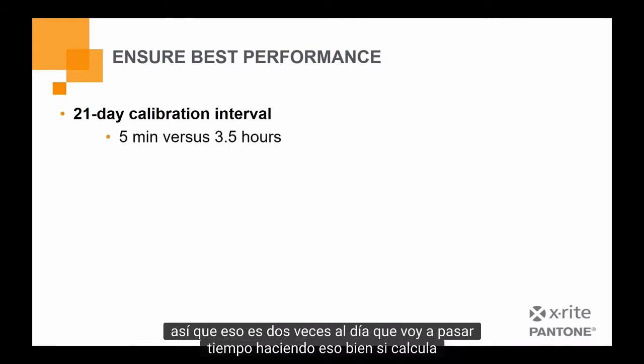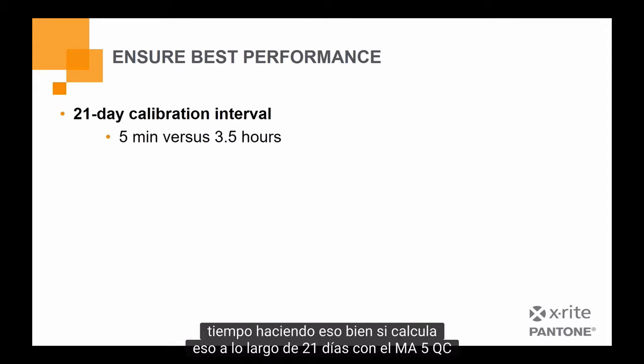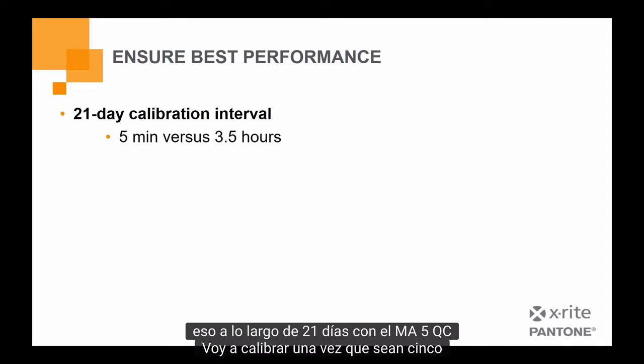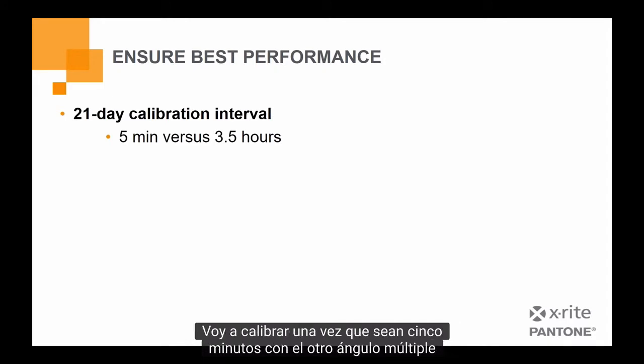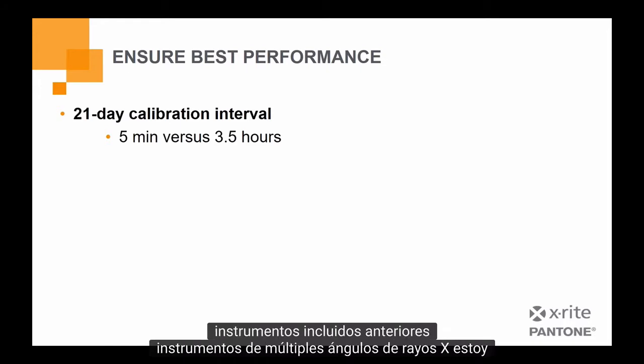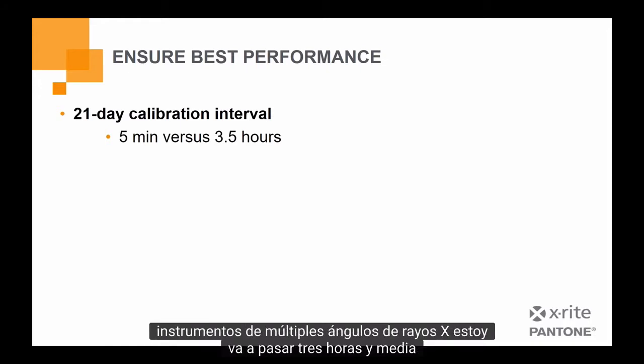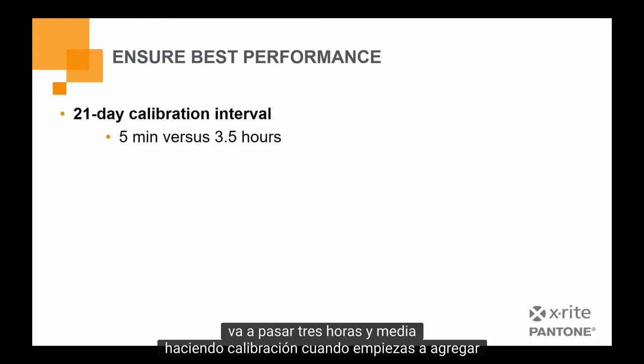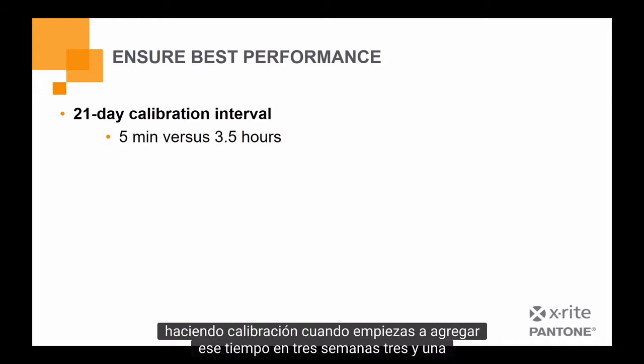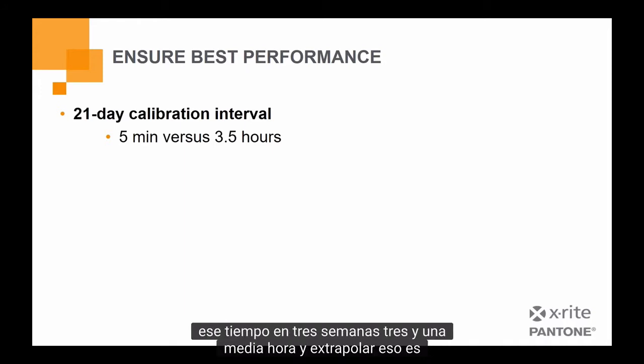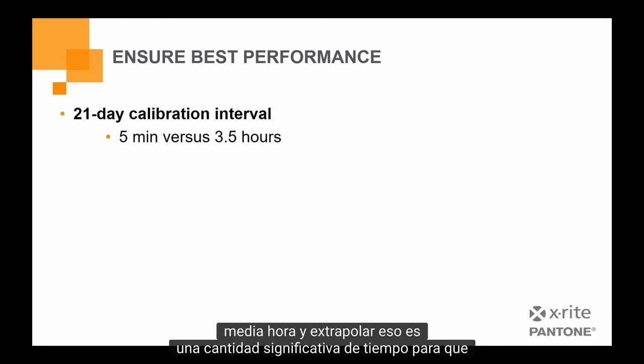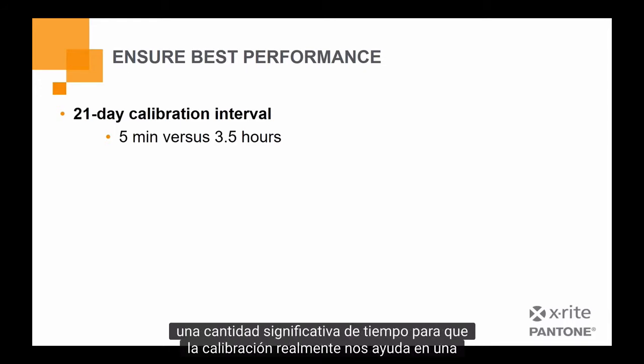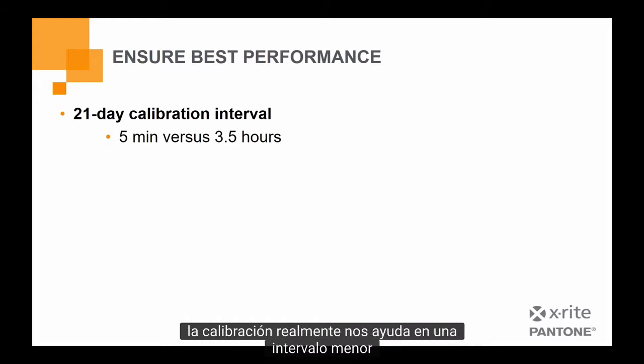doing that. Well, if you calculate that out over 21 days, with the MA-5 QC, I'm going to calibrate once. That's 5 minutes. With the other multi-angle instruments, including previous multi-angle instruments from X-Rite, I'm going to spend 3.5 hours doing calibration. When you start to add that time up, in 3 weeks, 3.5 hours, and extrapolate that out, it's a significant amount of time. So that calibration really does help us at a lesser interval.